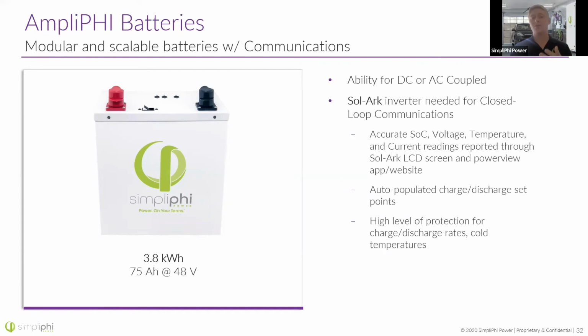I can only handle 1.9 kilowatts, so you're going to need to tone it down. As soon as you add more batteries to the bank, they will recalculate that charge and discharge rate and report it again to the inverter. So this is an advantage here, allowing your customer to start with a small system and scale up as they go.